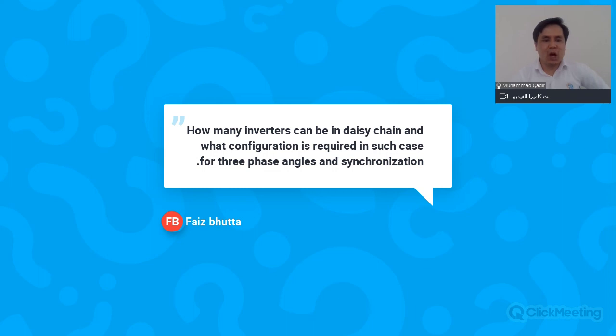Mr. Faze is asking how many inverters can be in a daisy chain, and what configuration is required in such a case for three-phase angles and synchronization. You can daisy chain inverters for communication purposes, and we had a special slide for this daisy chain where I said that each COM port can accommodate up to 30 solar inverters. So from 1 to 30, you have the option of doing a daisy chain of solar inverters.